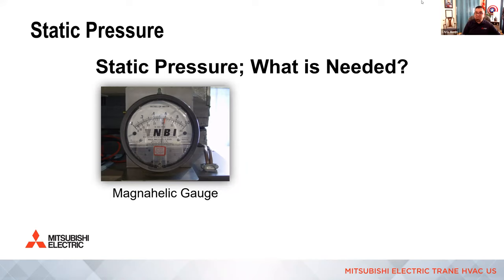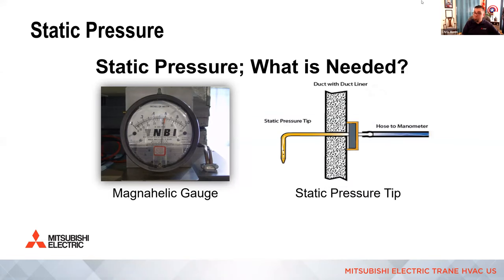So in order to measure static pressure, I personally have used a Magnehelic in the past. These days we use manometers. They're digital. They give you a much quicker, more accurate number. But all you need is a Magnehelic or manometer. I highly recommend a dual input manometer that reads Pascals. 25 Pascals is a 10th of an inch, right? So it's just the metric version, but it's more accurate.